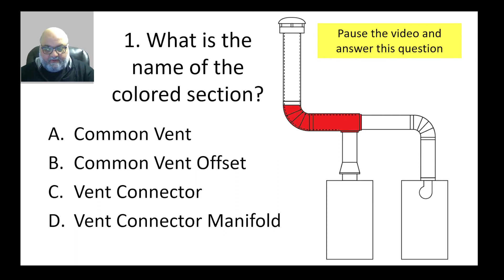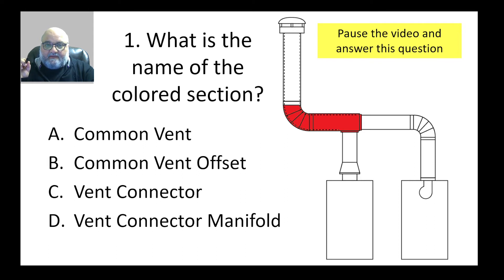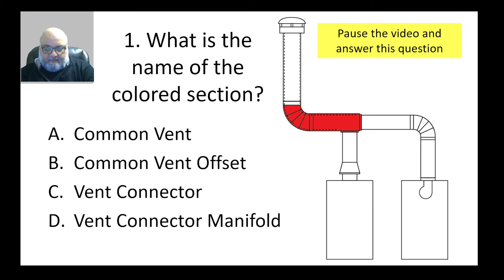This is the second section of the lecture on Chapter 3, Unit 22. We've talked about the definitions starting in Annex C — the manifold, the offset — and there are only two mutually exclusive types of appliances: fan-assisted or natural draft. There are also only two types of common vent or main vent: Type B or masonry chimney.